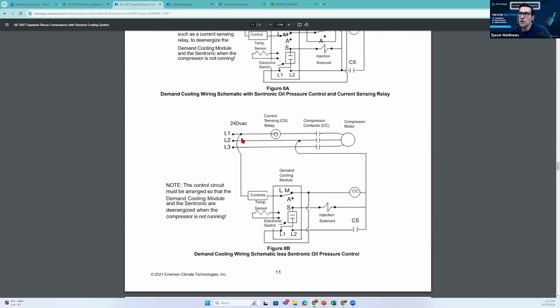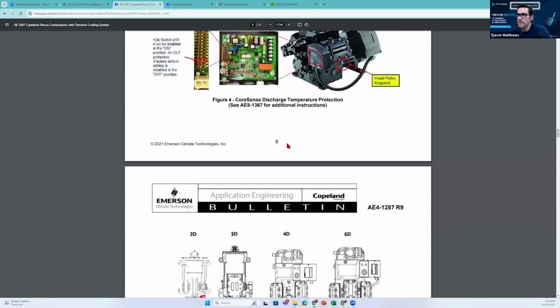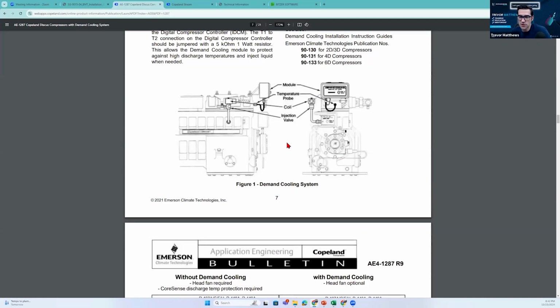there and troubleshooting, one of the things that you have to do when you're servicing a compressor, doing a maintenance, you drop the oil out. Just say you have to do an oil change. Pull this sensor out and clean it. It's going to be dirty. There's going to be carbon on it. Clean it out. Take a Scotch brush and just clean it off, and then put it back in.